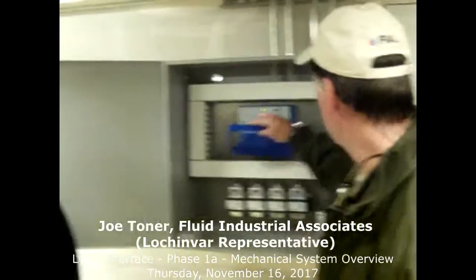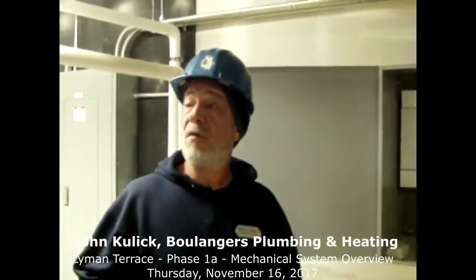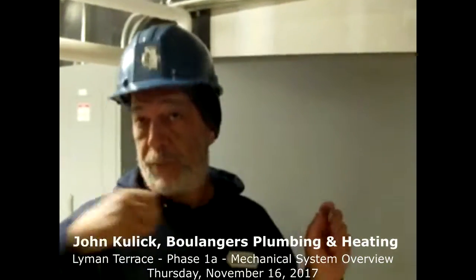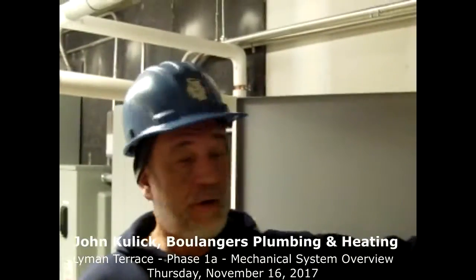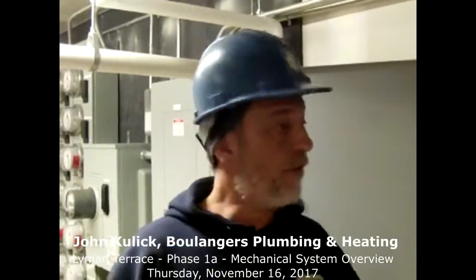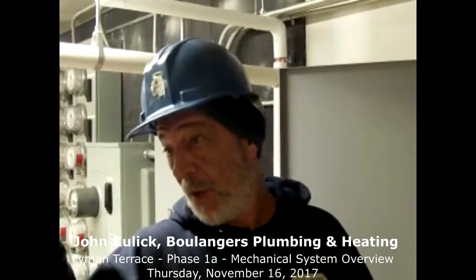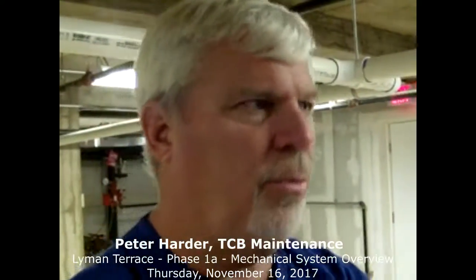So back to the duty cycle, you're saying, where should I come down once a month and change it? Pardon me, those circulator pumps are already doing that through this control. The only ones that don't do that are the recirc pumps on the wall there for the domestic hot water. Those are the ones that you were manually changing when we were walking around the other time. Yep. We manually change those once a month and do a weekly inspection of this and the boiler. Correct. That will be our weekly.